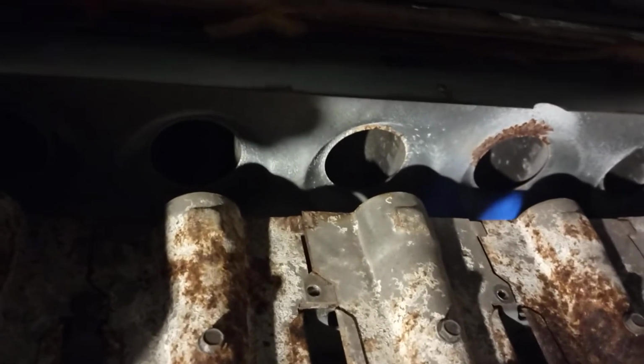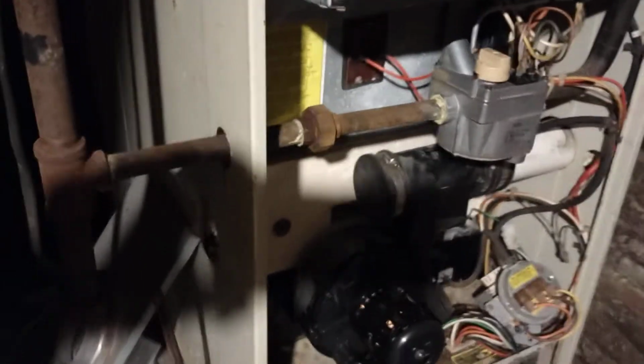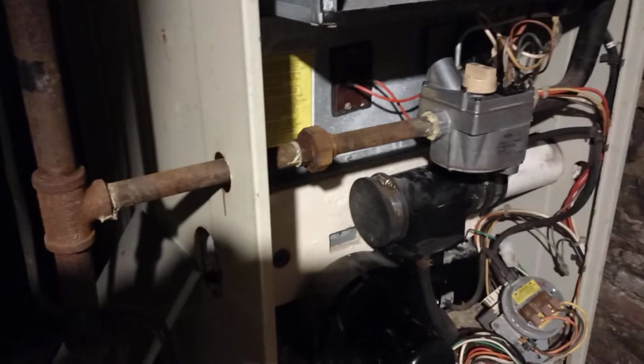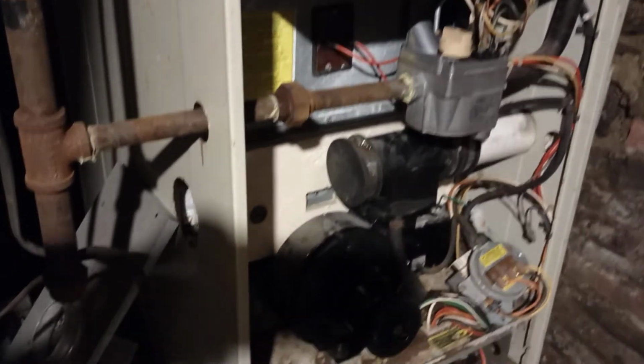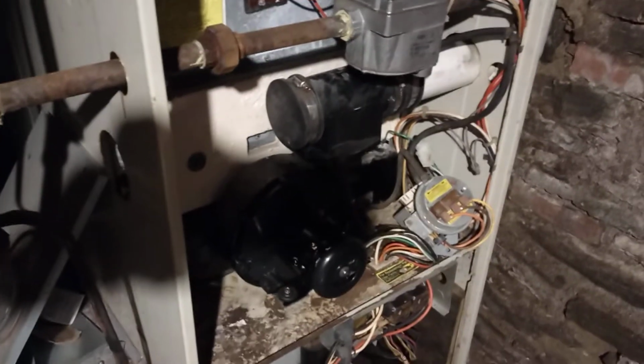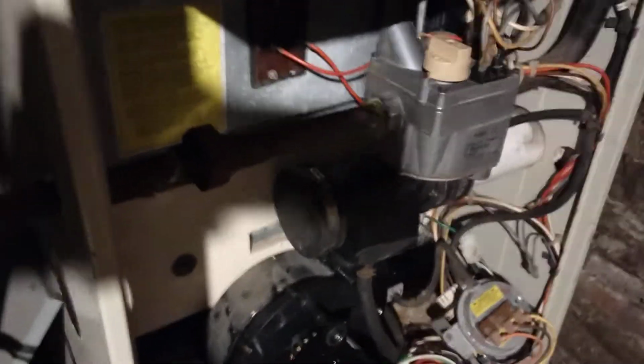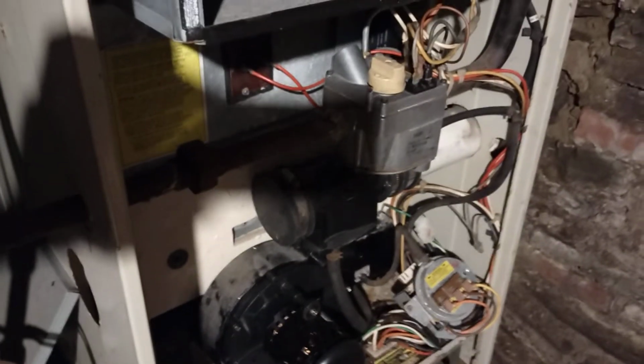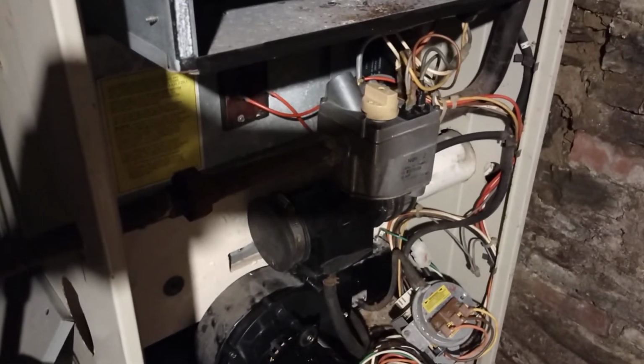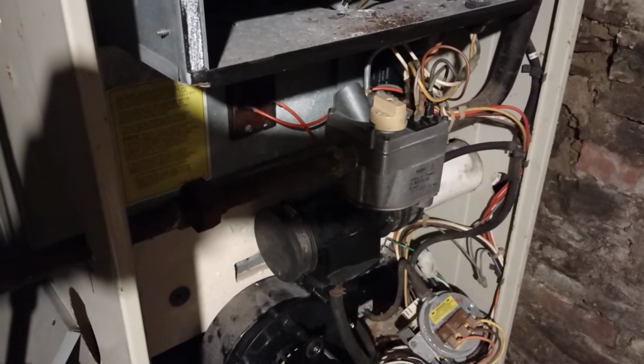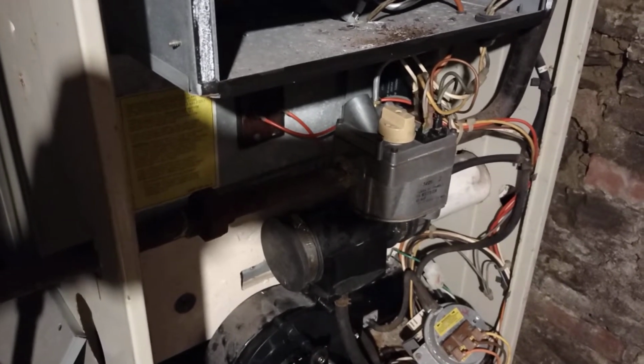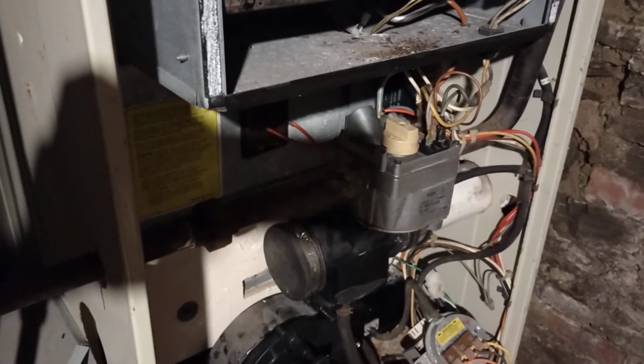You see here, pilot, please turn on. Now we gotta wait a few seconds, maybe 30 seconds to a minute, for the vacuum, to see whether the vacuum will get sufficient. Over here, your pressure switch - if the vacuum is enough, you'll start seeing that will open up a switch that will allow the main gas valve to open.